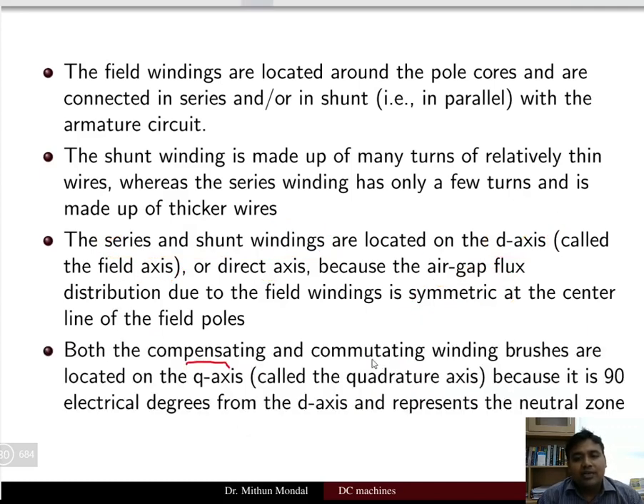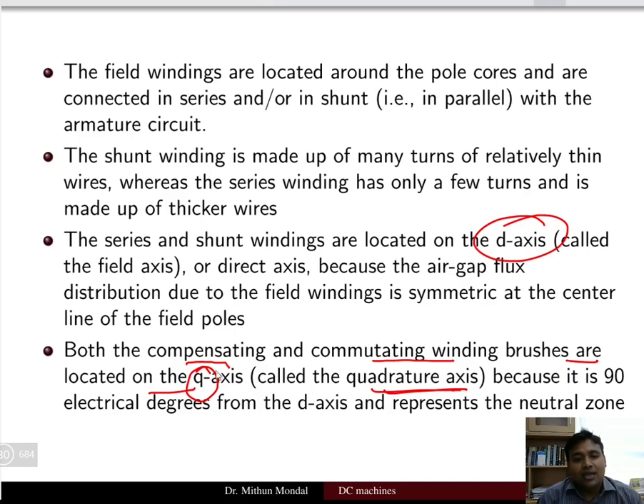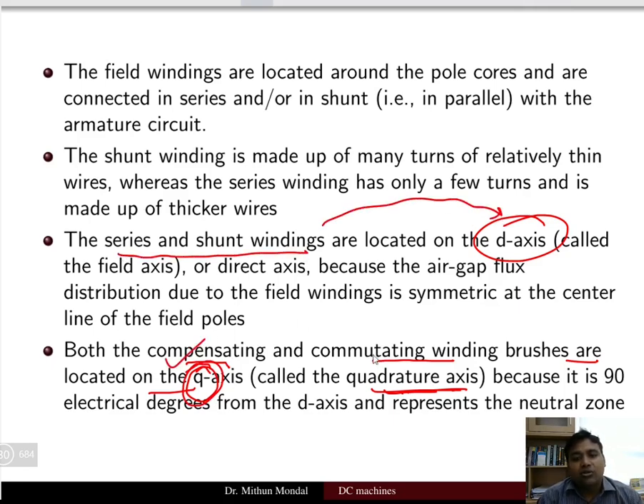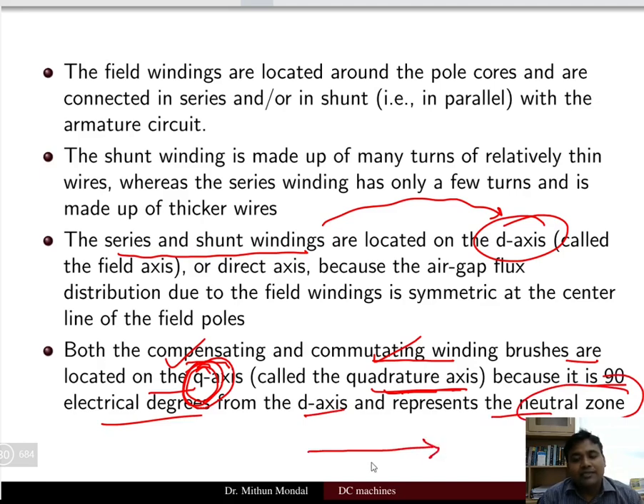Both the compensating winding and commutating winding are located on the Q axis, or quadrature axis. The Q axis is at 90 electrical degrees from the D axis and represents the neutral zone. So the main field pole lines are along the D axis, and 90 degrees away you have the compensating and commutating windings.